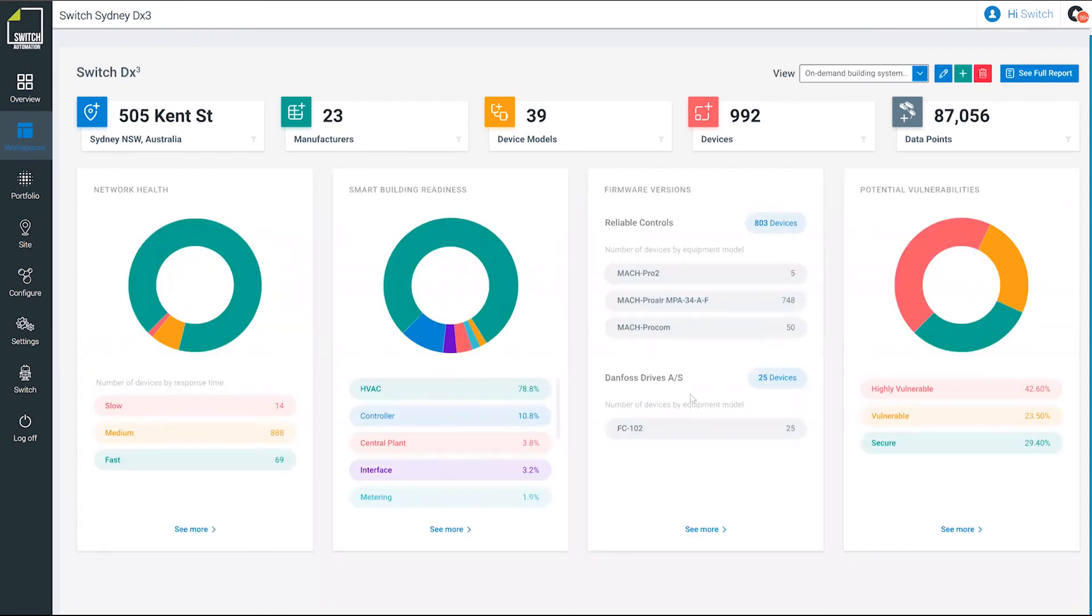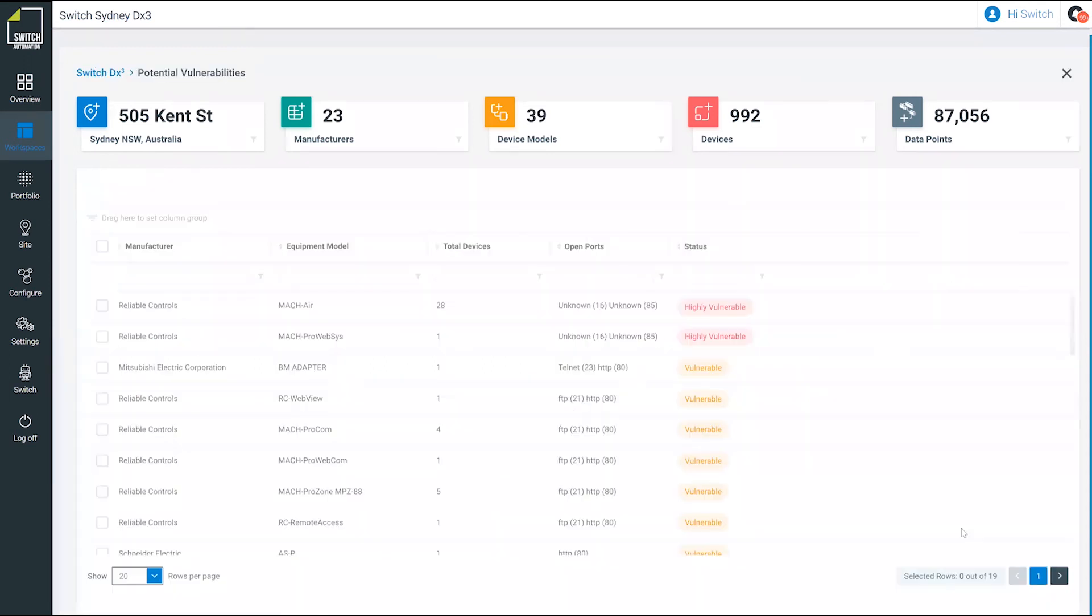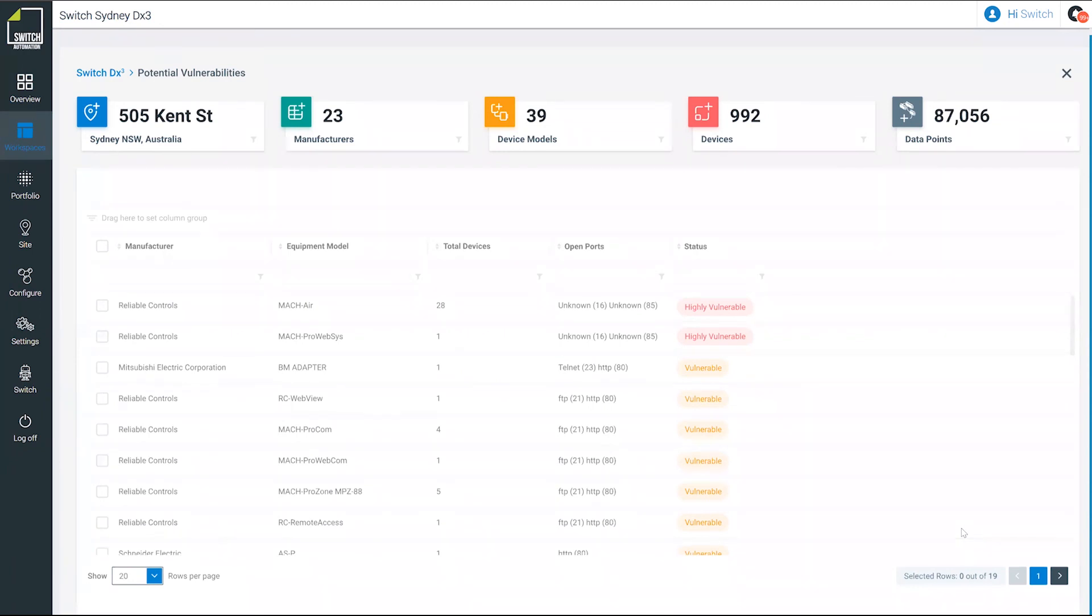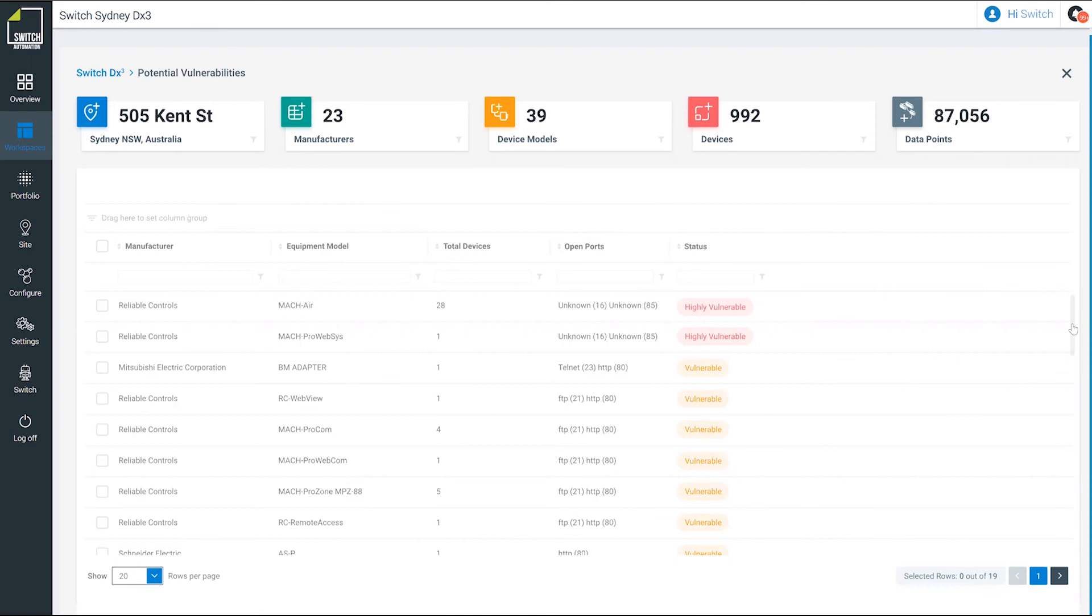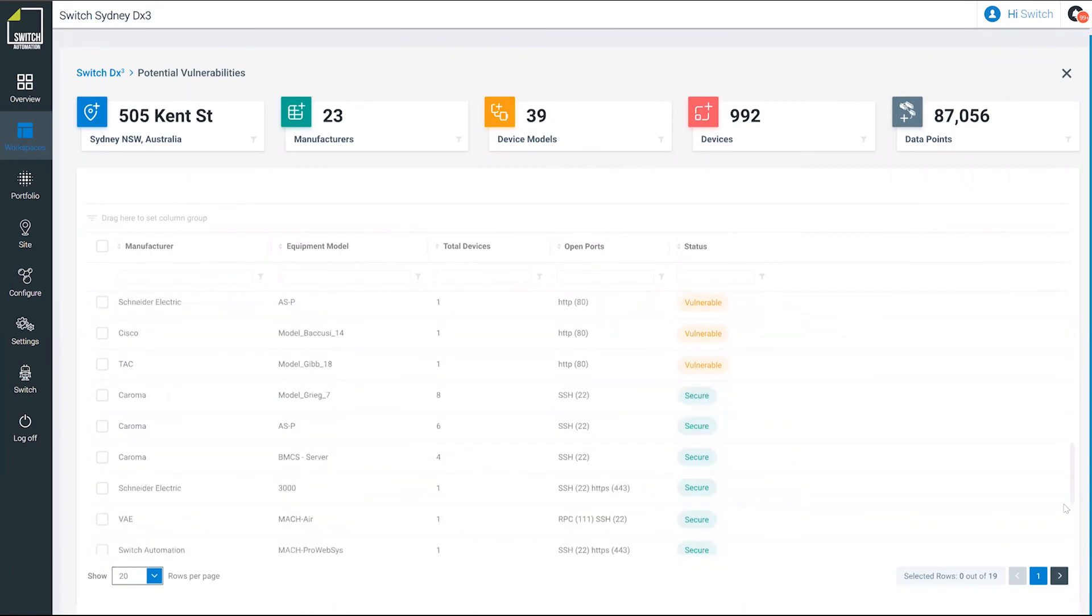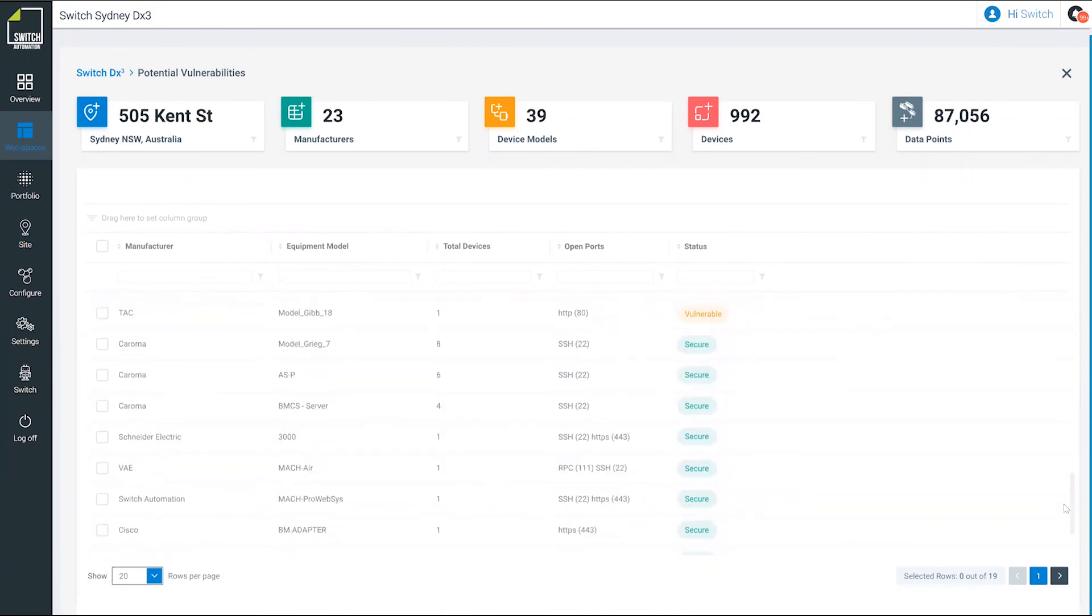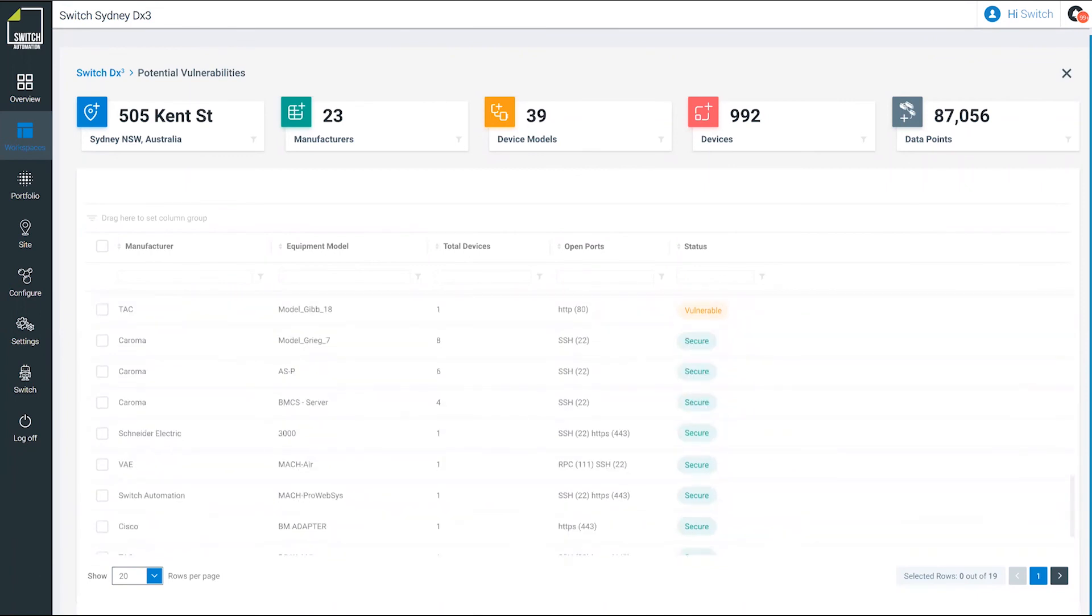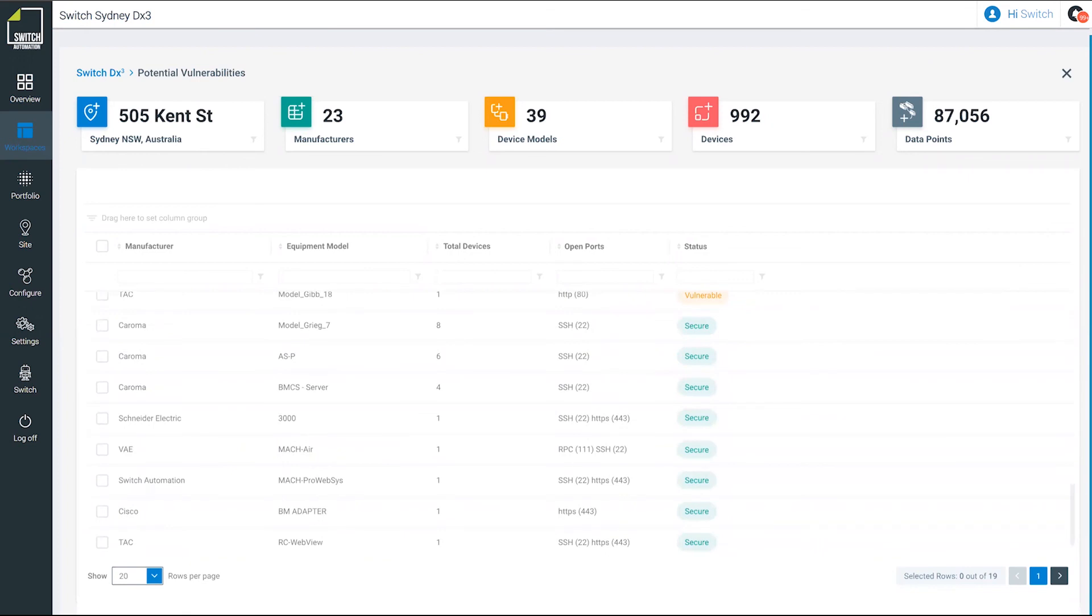The other thing that we do finally is really scan because we're doing this on the IP network. We're looking for potential vulnerabilities in the ports. We're not testing whether these ports have exposure to the internet because we're internally on this network. But what we can find and highlight to operations teams and maybe they get some validation from their IT teams is if these ports are exposed out to the internet. A lot of people probably on the call are very familiar with some of these ports. Port 80 is typically a web port to configure hardware. You're going to see that that's open. We're also going to see some secure ones, SSH ports, 443, HTTPS. We're actually doing this discovery.